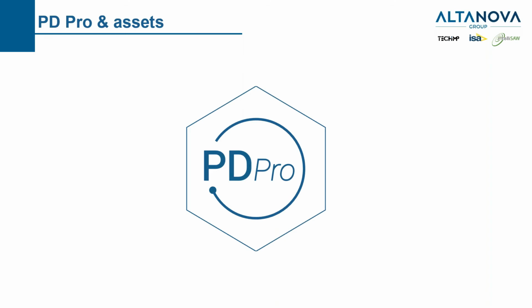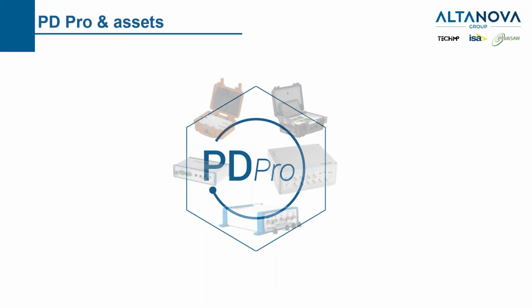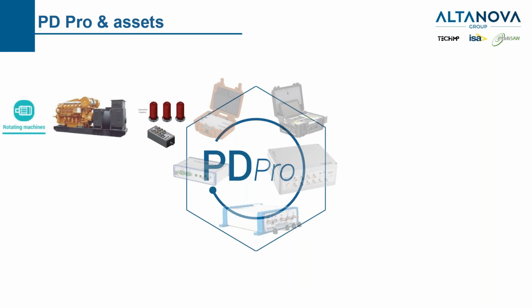Now, we can talk about PD Pro and assets, because we have seen the compatibility of the PD Pro just referred to Techimp family instruments right now. Actually, it is embedded, so we know that right now PD Pro can work with Micro Aquila, Aquila, PD Base 2, Falcon, PD Scope, and so on. But this is not referred to asset. Is it possible with PD Pro to test a generator? Yes, it is, obviously. There are several things that we can do on the generator.